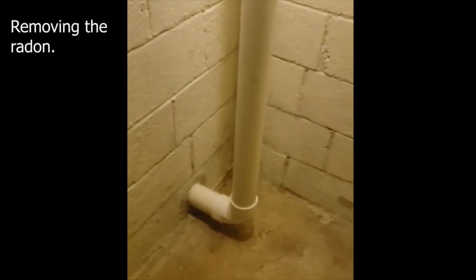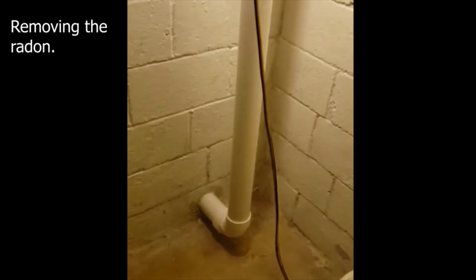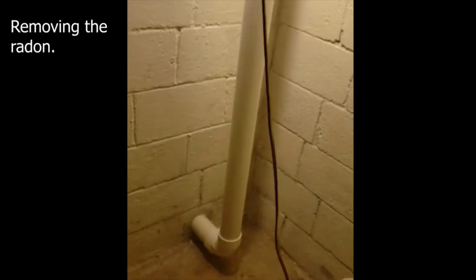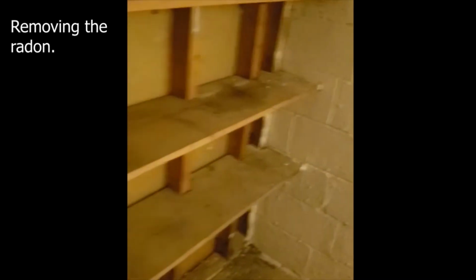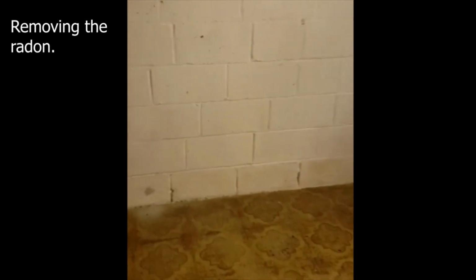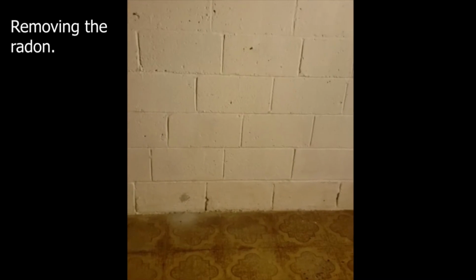We have our suction hole and the pipe leads to the outside fan. This is taking care of this entire wall that we were having high levels on, between 1,000 and 1,400 picocuries. Again, we were able to communicate through the other side wall. And again, this is where our pilot hole was, and we were able to communicate.